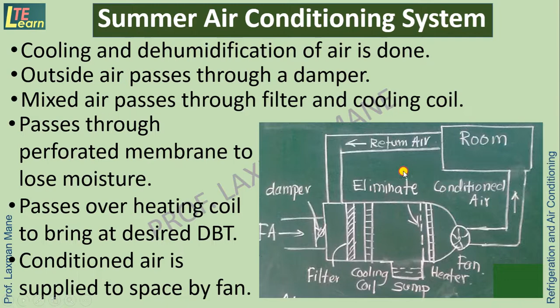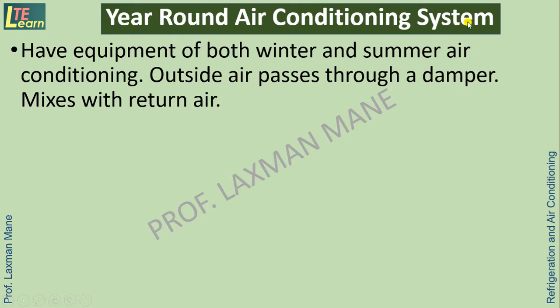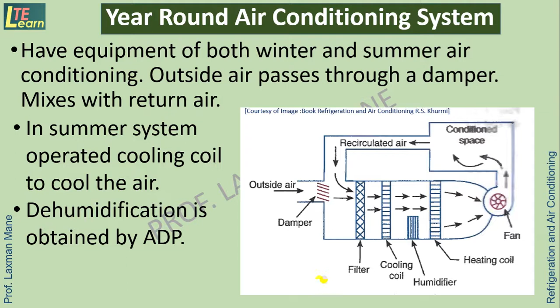Year-round air conditioning system is a combination of both. That's why year-round air conditioning system has equipment of both winter and summer air conditioning. In this case, outside air passes through a damper. Then it is mixed with return air. When the season is summer, then in this case system operates cooling coil in order to cool the air. Dehumidification of the air is carried out by maintaining the temperature of cooling coil below the dew point temperature. That is what we call apparatus dew point.